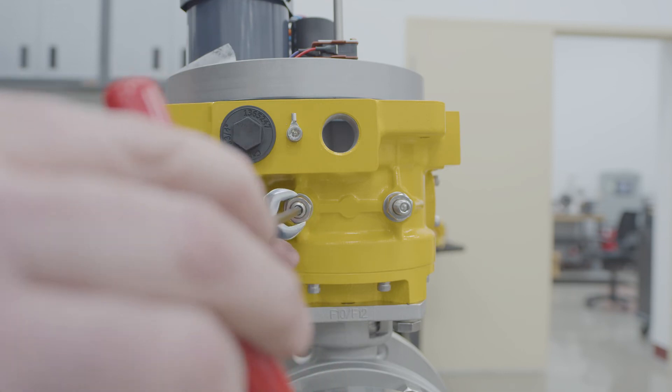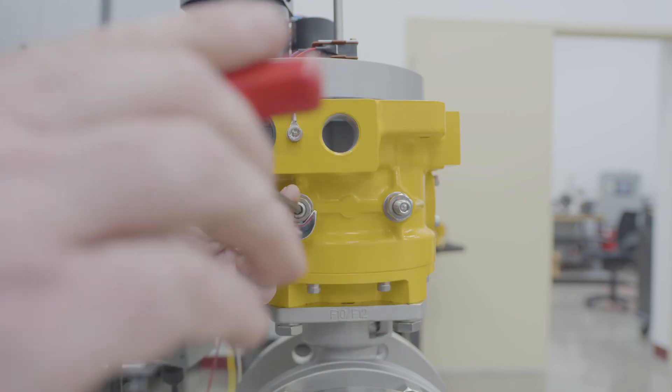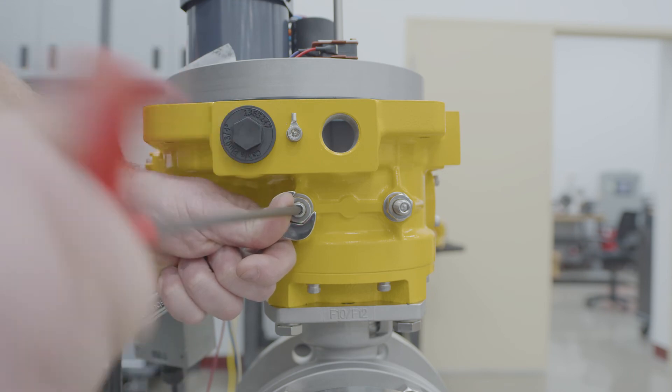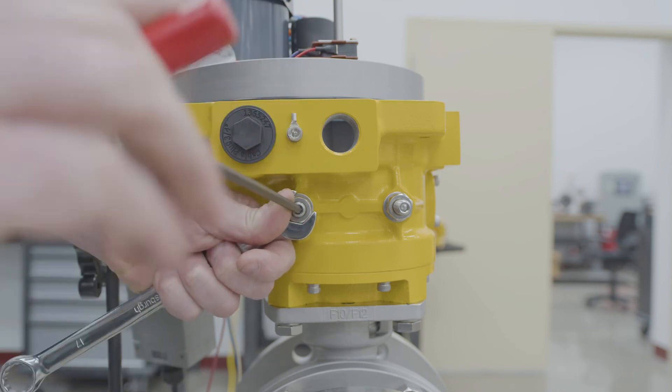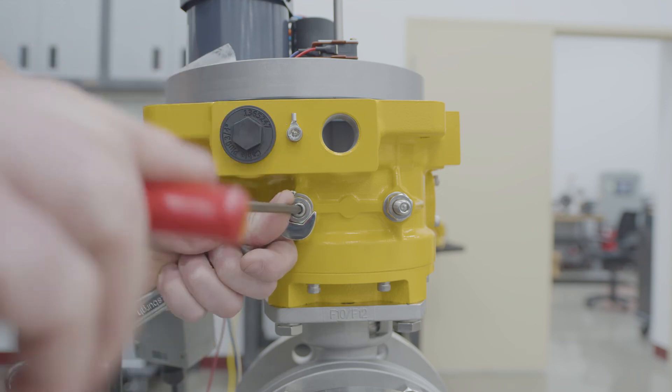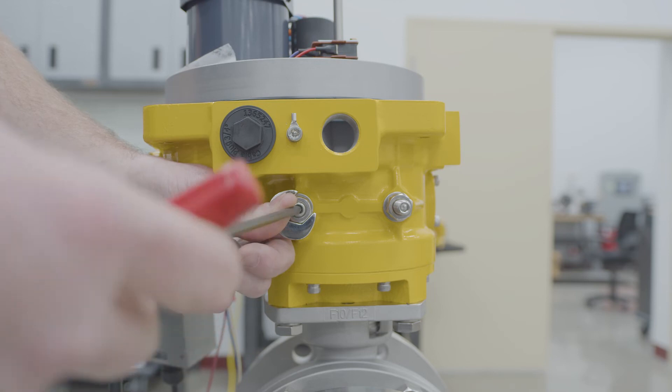And you want to run them in. This one's the open, and the valve's sitting in the open position. So you're going to run this in until it stops. After it stops, you back it off between two and three turns. I usually do two and a half.